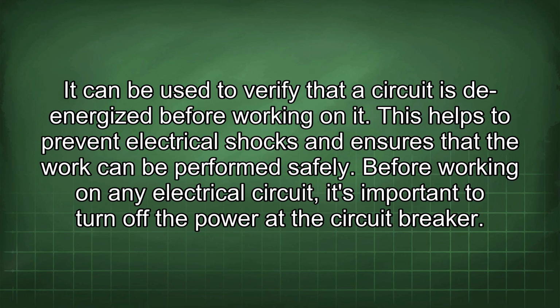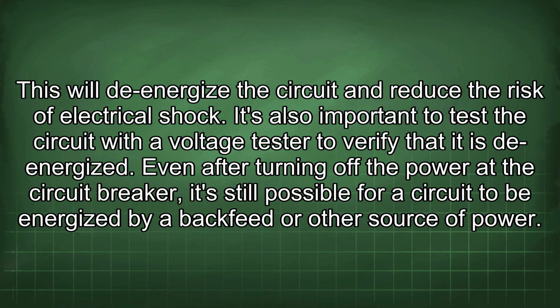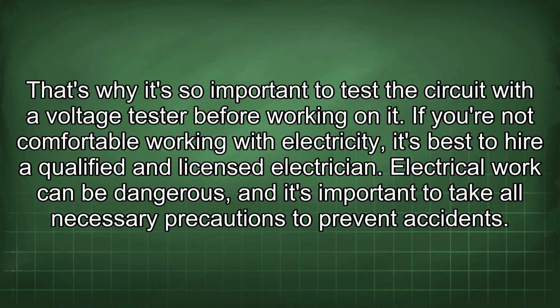Before working on any electrical circuit, it's important to turn off the power at the circuit breaker. This will de-energize the circuit and reduce the risk of electrical shock. It's also important to test the circuit with a voltage tester to verify that it is de-energized. Even after turning off the power at the circuit breaker, it's still possible for a circuit to be energized by a backfeed or other source of power. That's why it's so important to test the circuit with a voltage tester before working on it.